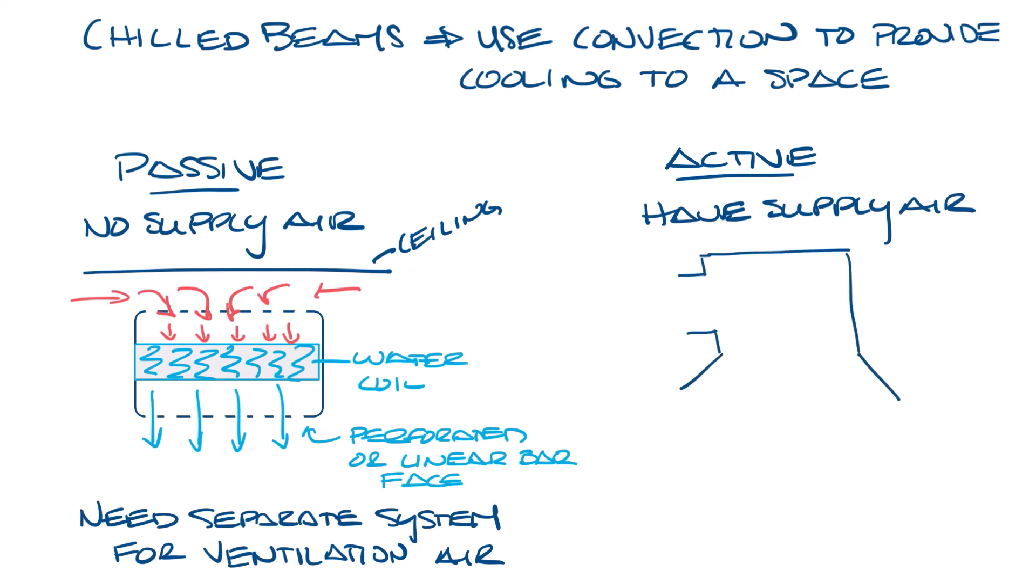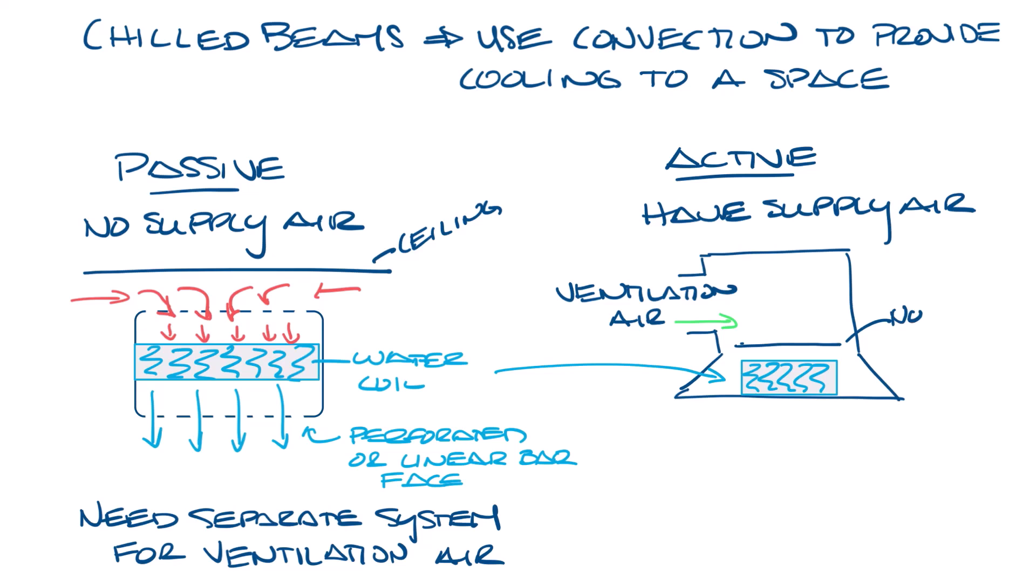An active chilled beam will look something like this. You have your coil and you've got the supply air inlet for ventilation air. It also has induction nozzles. So it works like this. Supply air comes into the primary air plenum section and goes into the induction nozzle and then out slots in the face of the chilled beam, similar to a regular slot diffuser. And this whole thing would be mounted above the ceiling with the face flush with the ceiling. The air leaving the slots creates a low pressure zone at the face of the active chilled beam, which draws air up into the chilled beam and over the cooling coil, where it'll mix with the supply air and then go back out the slots.